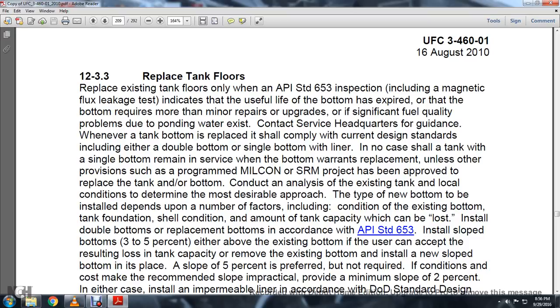When tank bottom replacement is required, the new bottom should fully comply with current design standards including double bottom, single bottom, and liner options. If the tank shell has a single bottom with remaining service life, the bottom should be replaced unless other provisions are programmed under an approved MilCon SRM project. Conduct an analysis of the existing tank and local conditions to determine the most desirable approach and type of new bottom. Factors include the condition of the existing bottom, tank foundation condition, and the amount of tank capacity that can be lost. Install double-bottom replacement in accordance with API Standard 653.